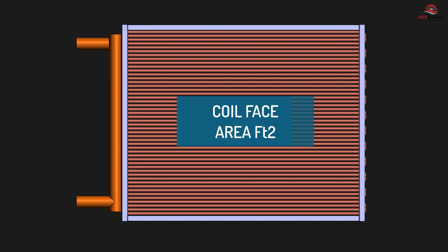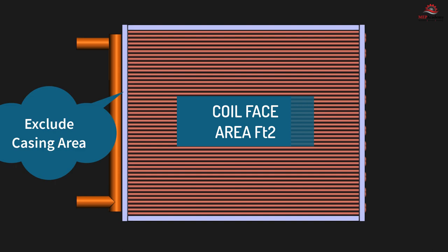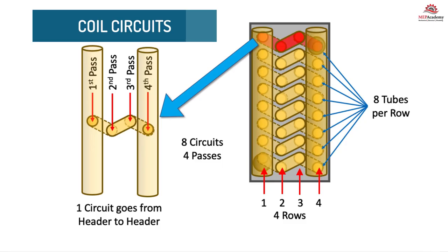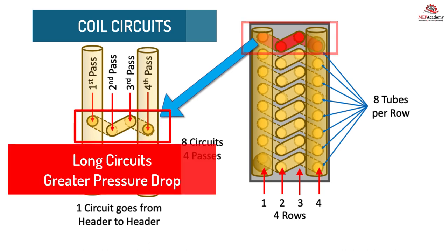The face area is considered that portion of the coil which air passes through, excluding the casing area. To calculate the face area of a coil, you measure the height and length from the inside of the coil casing. Circuiting refers to the path of travel from when the water enters the coil until it leaves. The circuit starts where the tube attaches to the supply header and travels back and forth until it attaches to the return header. The longer the path for the water, the greater the pressure drop and the lower the flow rate, giving the water more time to absorb or reject heat.